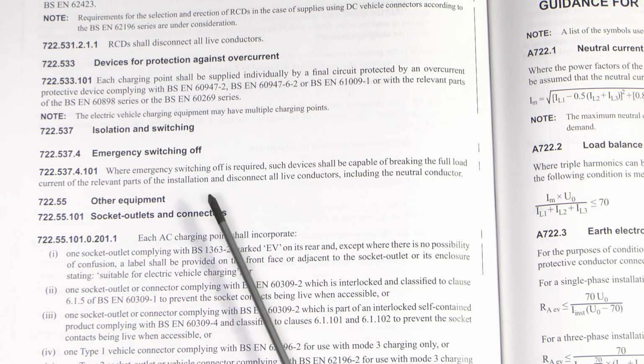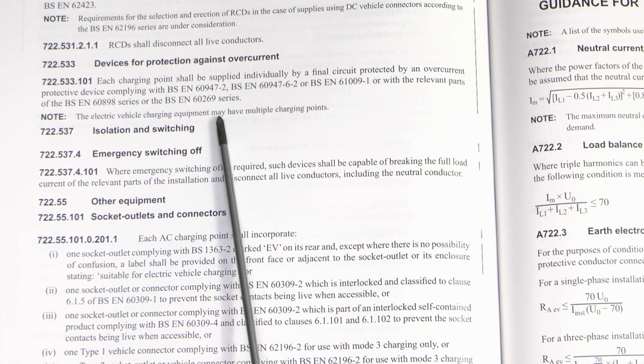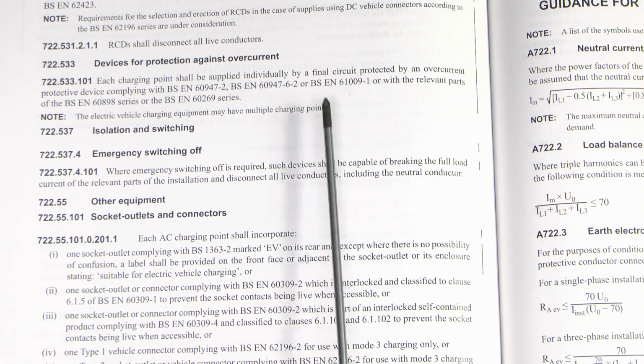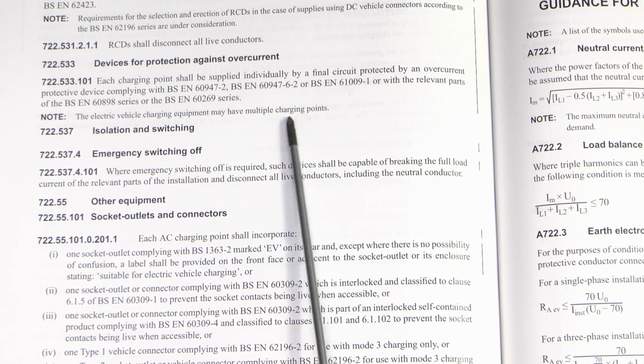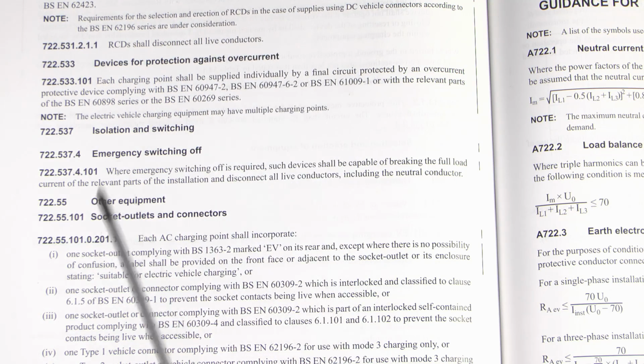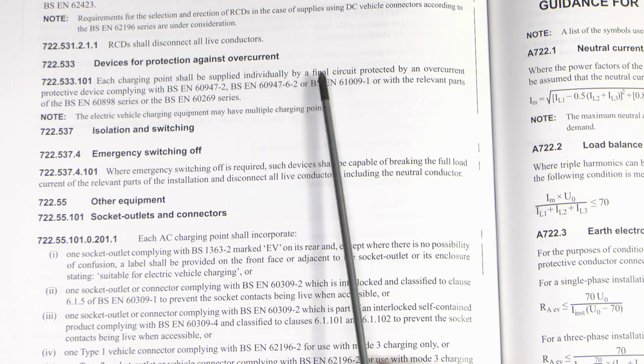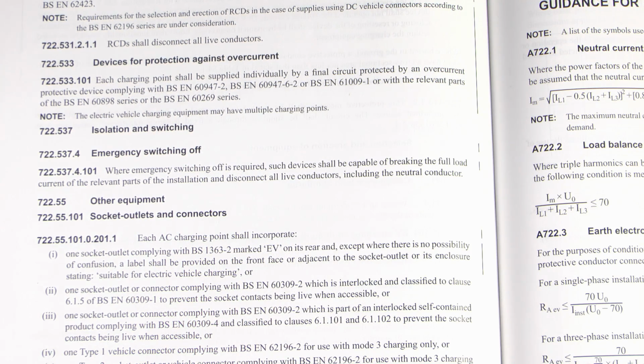And again, generally people are going to have one certainly at their house there. And I know here that the charging equipment may have multiple charging points, so if you have a device that say had two connection pieces on it, that can be supplied from one circuit, but if you're putting in two separate charging outlets, then those need two separate circuits for those.